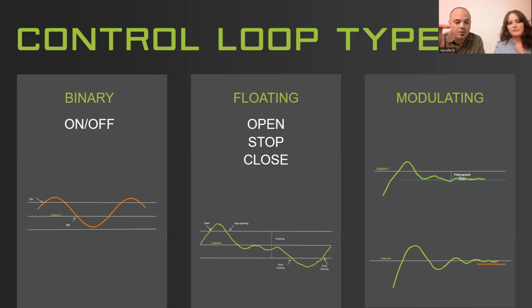It's still going to measure temperature versus the set points. And as the deviation gets big enough to call for that compressor to turn on, it's going to flip it to an on state and leave it on until that temperature is satisfied, and then turn it back off. Pretty straightforward. That's the general application you're going to see a binary loop associated with. And so moving on from there, we're getting into floating and modulating. The most common application I'm going to refer to here involves valve actuators. Floating and modulating are different ways to achieve a similar result.